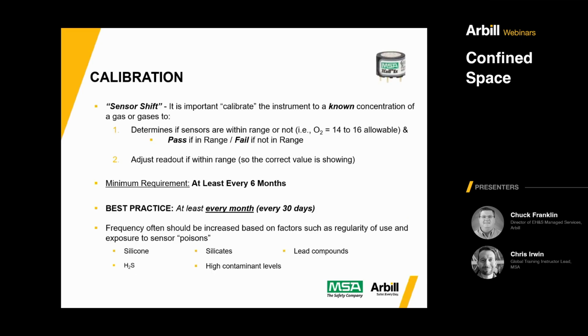Something that is really important is this concept of calibration. I'm sure a lot of you here generally know what calibration is, but we need to make sure that the readings the detector is giving us are correct. And what we will do, and we'll have a picture of this in a coming slide, is take a bottle of what I call bad gas, where we have a known concentration of low oxygen, a flammable substance, carbon monoxide, H2S, all those things. And we will put the detector in test mode, calibration mode.